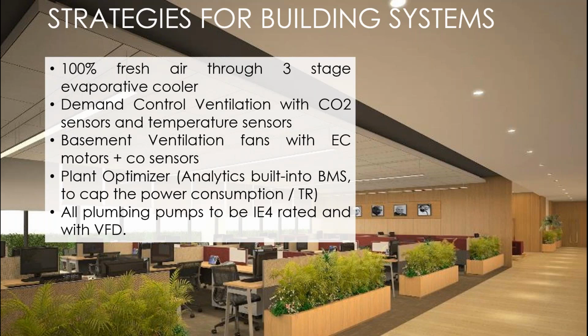We should also know that VFDs result in harmonics, which is a big issue in buildings these days, and you have to put in harmonic filters. So we remove VFDs, we remove harmonic filters. These EC fans are DC motors, 0 to 10 volts, and they can give me the same variable performance which a normal DIDW fan with a VFD gives.